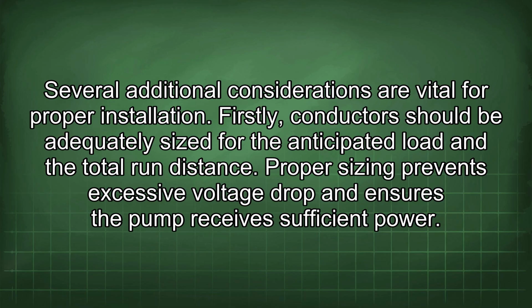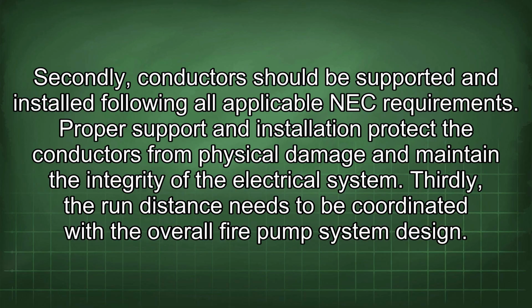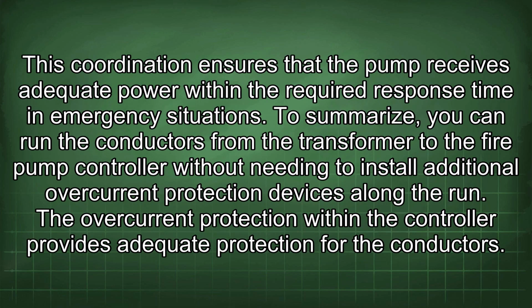Several additional considerations are vital for proper installation. Firstly, conductors should be adequately sized for the anticipated load and the total run distance. Proper sizing prevents excessive voltage drop and ensures the pump receives sufficient power. Secondly, conductors should be supported and installed following all applicable NEC requirements. Proper support and installation protect the conductors from physical damage and maintain the integrity of the electrical system. Thirdly, the run distance needs to be coordinated with the overall fire pump system design. This coordination ensures that the pump receives adequate power within the required response time in emergency situations.